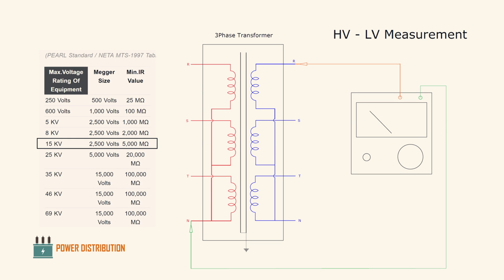Last but not least, we measure the high voltage to low voltage insulation resistance by connecting the line or hot probe into the primary or the secondary, and the earth probe to the secondary or the primary, or you can do it otherwise, it doesn't matter.